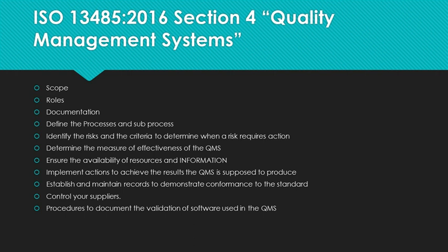You must establish and maintain records to demonstrate conformance to ISO 13485. You must control your suppliers — you are responsible for what they make and its impact on the medical device, and you should have written quality agreements with your suppliers. Responsibility for risk cannot be passed back to the supplier for ISO 13485. You must have procedures to document the validation of software used in the QMS, and software must be validated prior to initial use. This is a new requirement for the 2016 revision. Most auditors recognize that commercially available software such as Microsoft Word or Excel does not need to be validated, unless you are controlling the QMS using macros that you have written into one program or the other, in which case those will need to be validated.